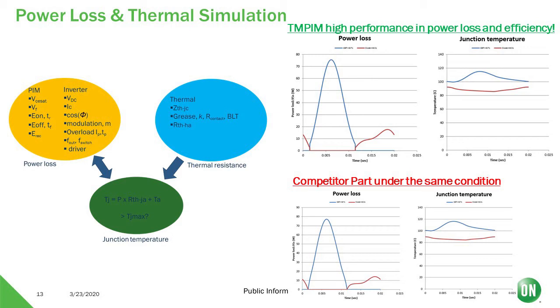With the thermal resistance of the power devices known, the temperature rise of the component can be calculated by multiplying power loss and the thermal impedance. TMPIM IGBT has a lower temperature, indicating it has good thermal resistance. A lower device junction temperature also means it can bear more power if the same temperature rise is allowed.